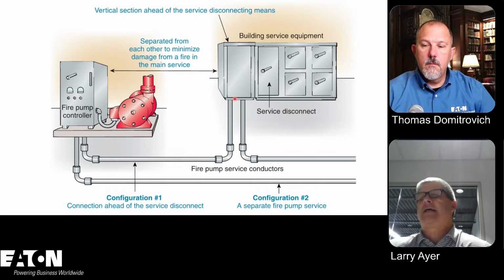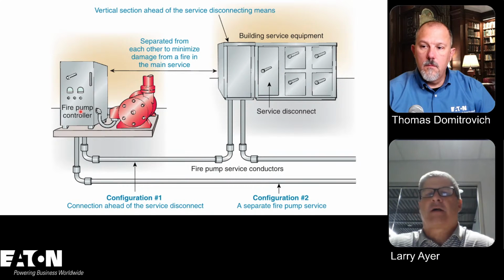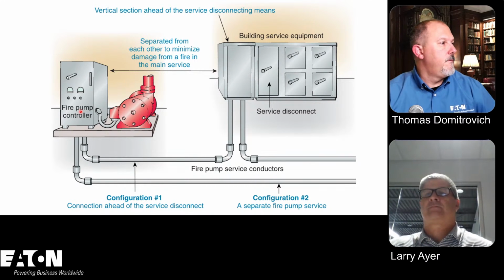A lot of what I see today might be in existing buildings, but in new buildings, most every time I see it nowadays, everybody's trying to put the metering at the transformer, come straight from the transformer into the building, and go directly up to the fire pump controller room. So you can do it both ways. There's nothing wrong with either way, but that is option number 1 on how to feed the fire pump. Cool.